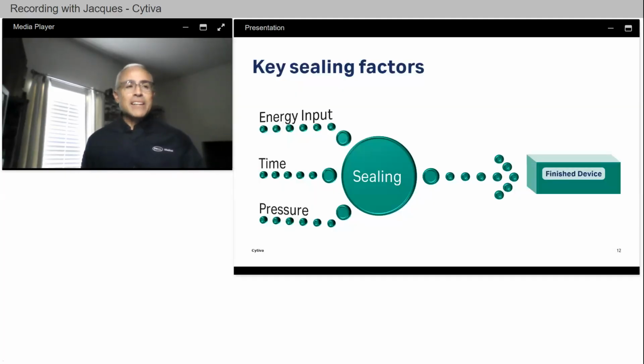So, moving to the sealing methods. You will notice that there are three parameters that are common to all four sealing methods. These are energy input, affecting the temperature of the components, time of exposure to sealing conditions, and assembly pressure holding the parts together, also referred to as force on the part. The specifics around each of these three parameters used for each of the sealing methods will vary, as they are dependent on the properties of both the filter material and the plastic housing to which it is being sealed.